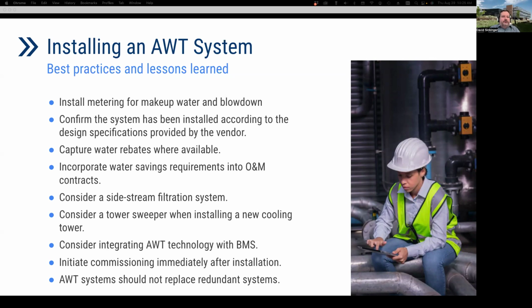Do suggest that you try to initiate commissioning immediately after installation. Sometimes the timing with cooling seasons can make this challenging, but your site should see proof of performance, and make sure that you receive the documentation, and make sure the contractor fixes any outstanding issues. And then the last bullet there is AWT systems should not replace redundant systems. So in one GSA installation, a redundant cooling tower heat exchanger for process cooling was eliminated. And later on, they found that that created issues for the facility.